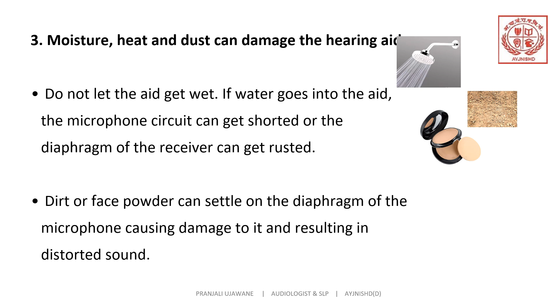Also, we should keep in mind that at night, we should keep the aid in a dry aid kit, which can be purchased from the hearing aid manufacturer. The material in the dry aid kit will absorb the moisture that may have collected in the hearing aid due to the sweat, etc. The moisture due to the humid weather can damage the microphone of the hearing aid. Replacing the microphone can be expensive.